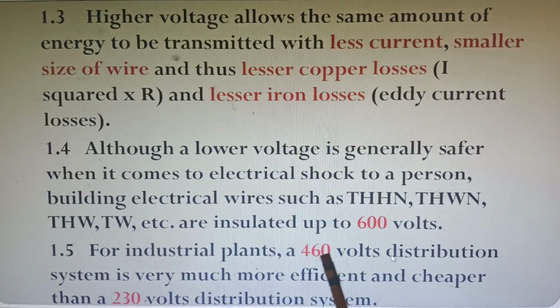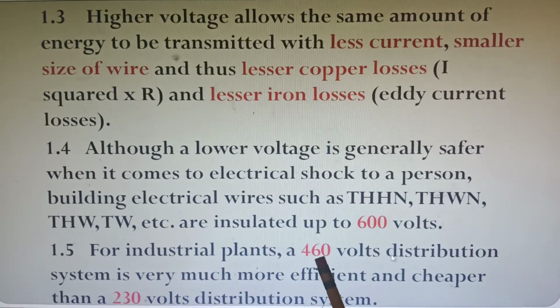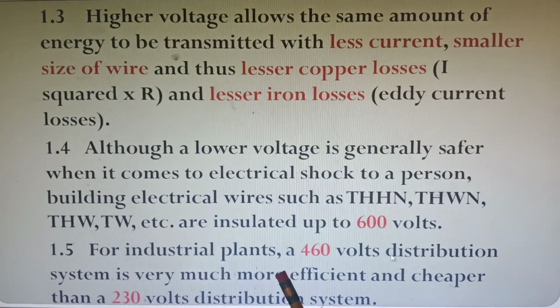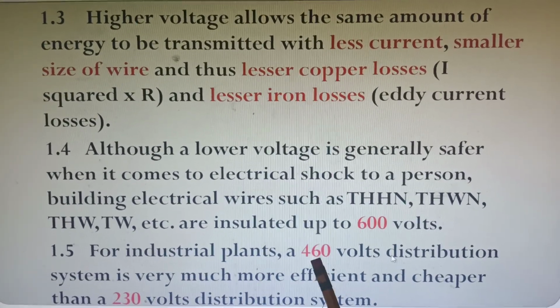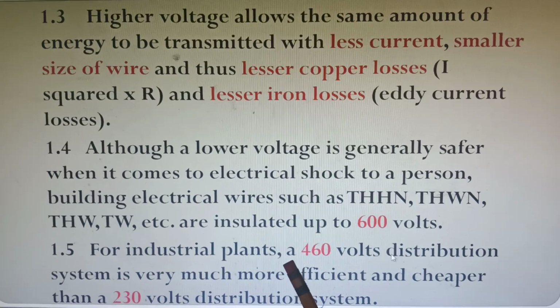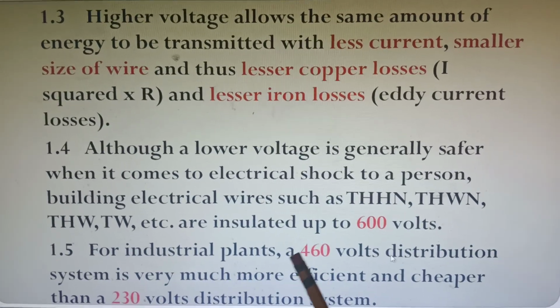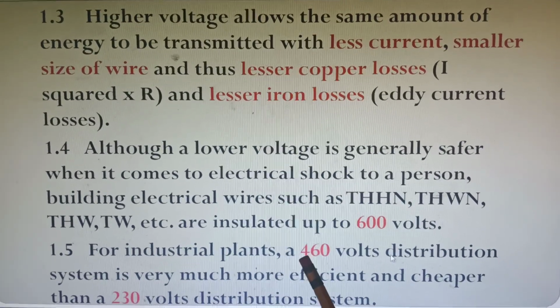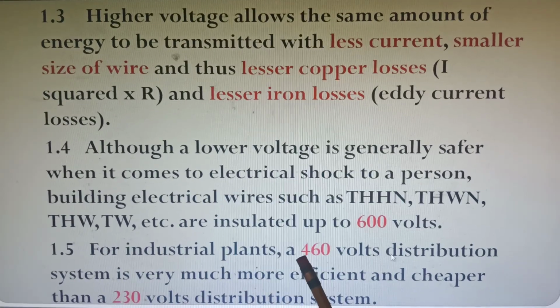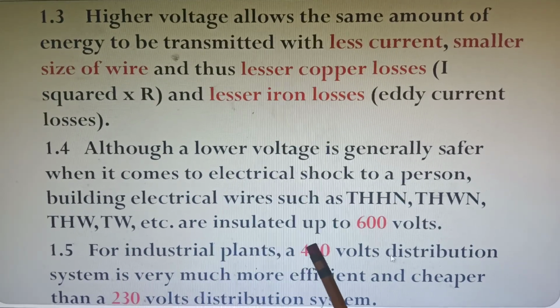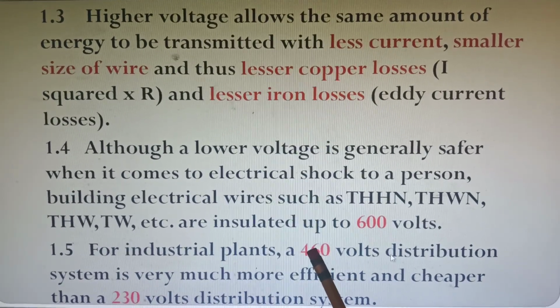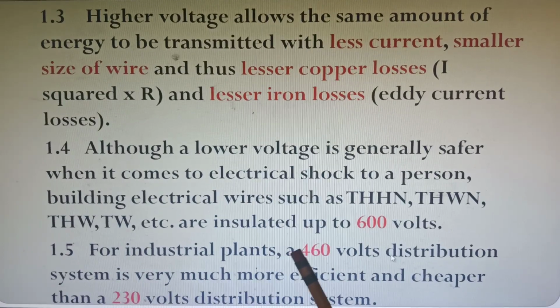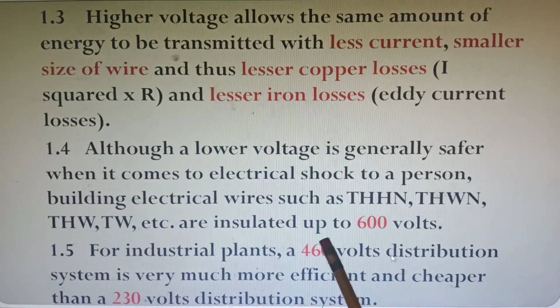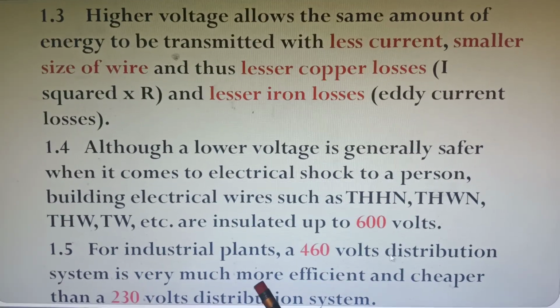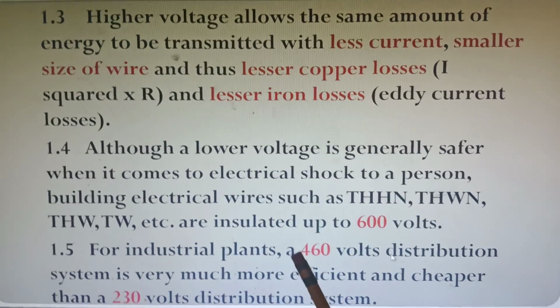The project manager asked me why I would change the system from 230 to 460. I told him there will be a lot of savings when we use 460. First, we will have smaller size of feeder wires, and smaller sizes of circuit breakers, because our voltage is 460 volts. So in the long run, there will be a lot of savings.